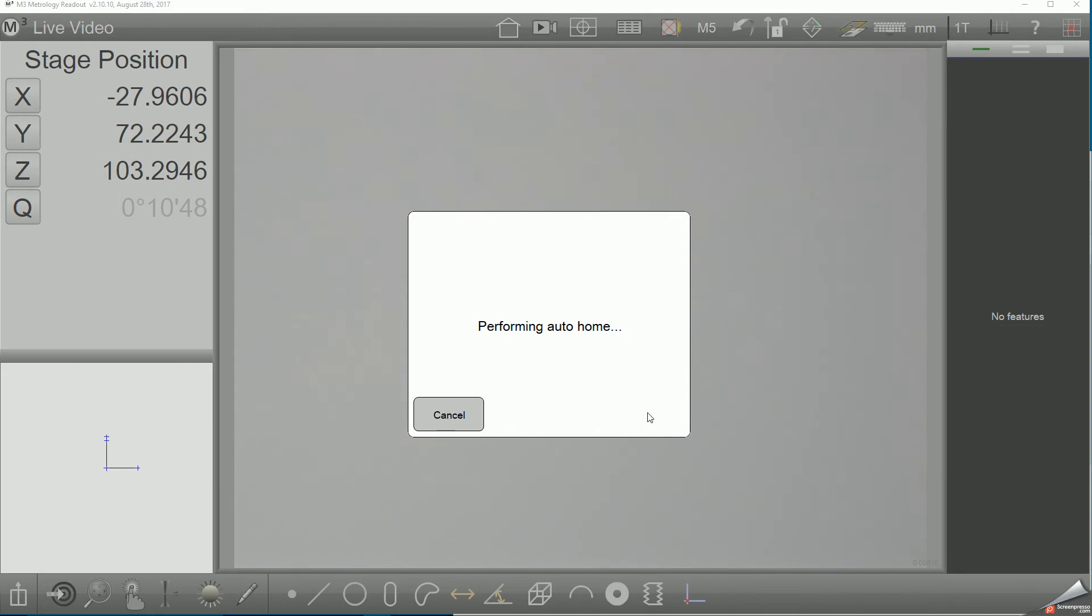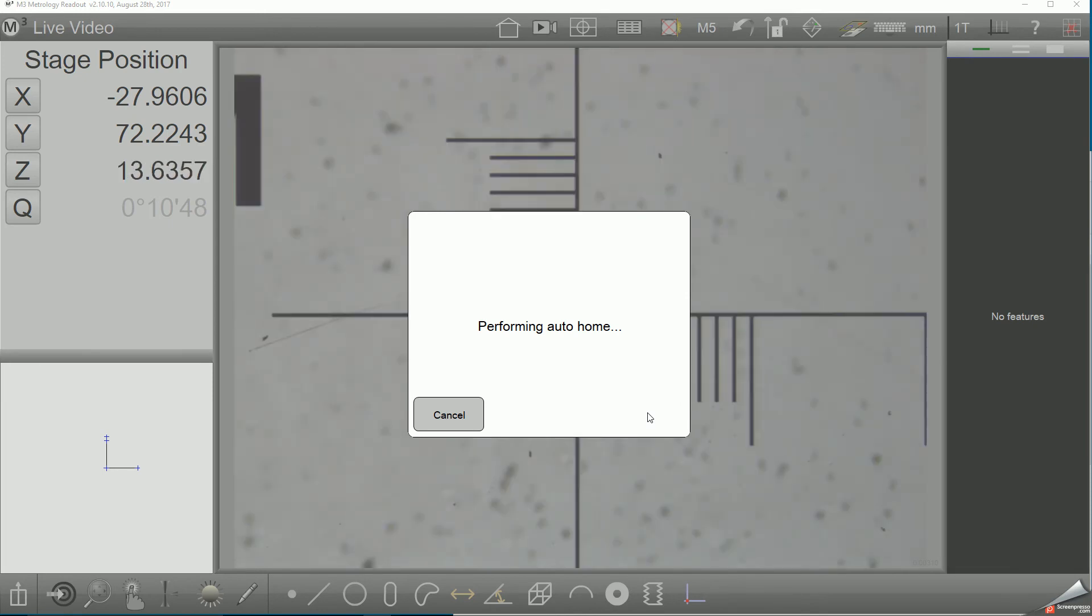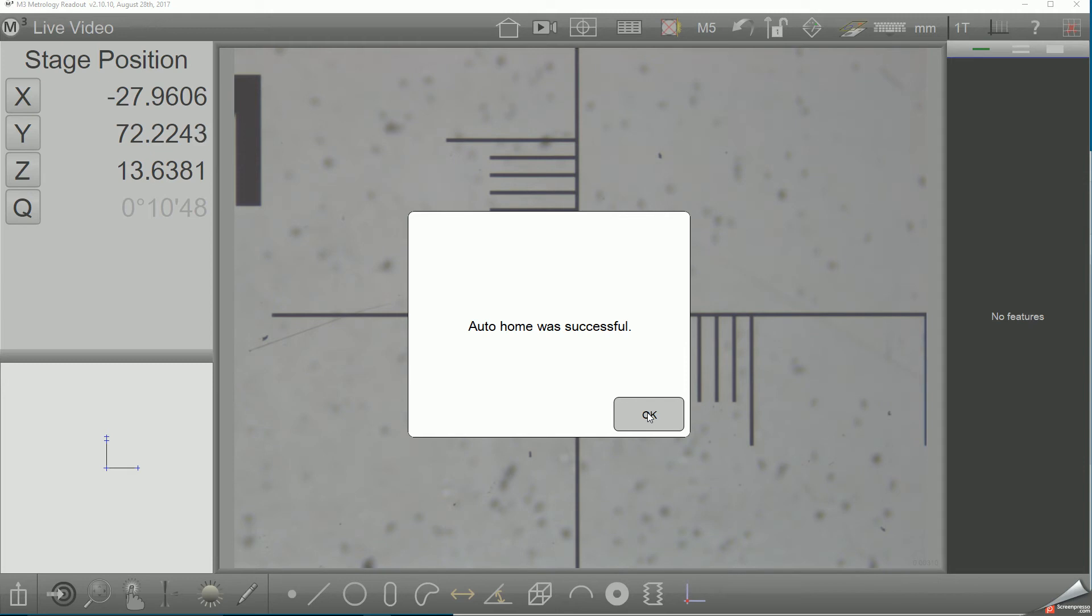It's quite common that the origin of the calibration artifact to be used will not be located on the stage at the same zero position as your machine zero offset, and as such a mapping offset is supported in the system. We'll describe that more when we come to that setup screen.